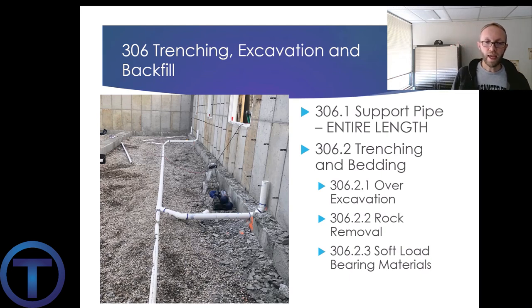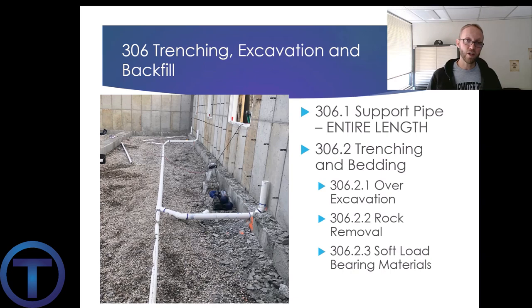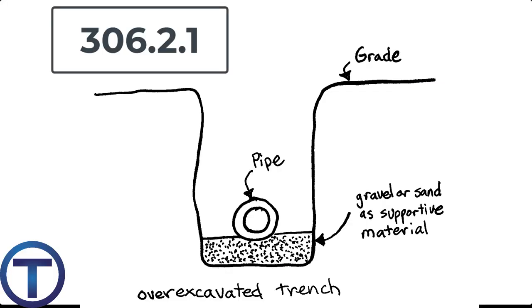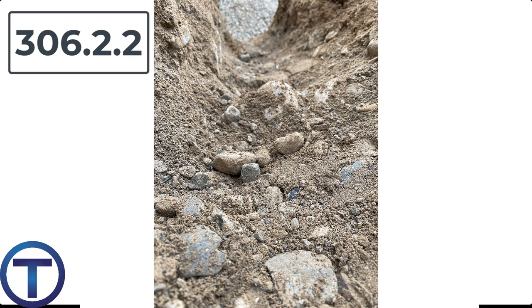306.2: Trenching and bedding. We look at over-excavation, rock removal, and soft load bearing. 306.2.1 over-excavation: if we dig too deep, we need to refill that trench to the level where the pipe will be with something supportive — gravel, sand, or compacted earth — not just loose dirt. For rocks, 306.2.2: if rocks would penetrate up into the pipe, we have to remove those rocks down to three inches below, then refill with something uniform and supportive to protect and support the pipe.